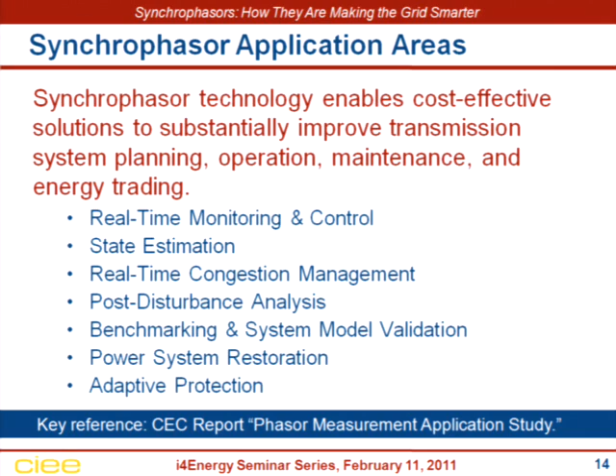So real-time monitoring and control, I talked about this. One thing you'd like to do is monitor phase angles in the system. I'll have a picture later on showing the phase angles of a system in terms of colors, where from one end of the system they're diverging from the other area. You have to keep an eye on this because it's an indication of the stability of your system. The farther apart the phase angles go, the more stress on the system, the more likely something will break. So operators would really like to have that kind of information.